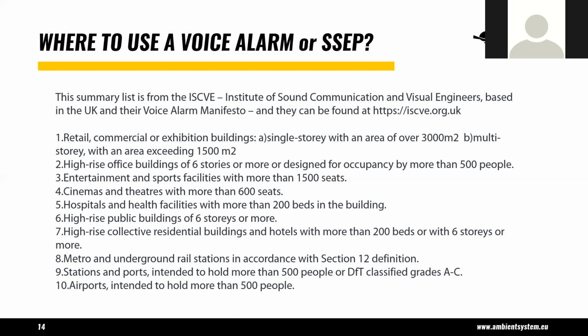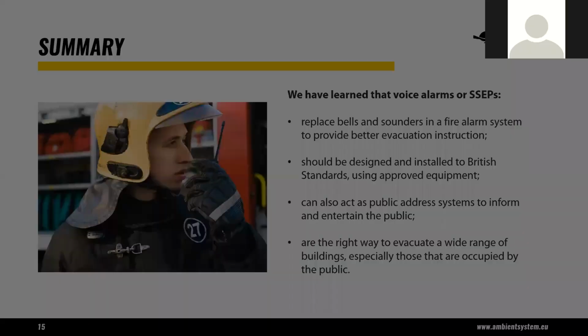So again, retail, commercial, exhibition buildings, particularly when they're multi-story, high-rise, entertainments and sports, cinemas, larger hospitals, and again, anything where the time to evacuate is longer, because high rise, by definition, gives you a longer time to evacuate. And once you turn the lifts off, which pretty much happens whenever you have a fire event, you start telling people to come down 10 or 12 flights of stairs in an orderly fashion, and that takes time. So this is why the high rise is a strong contender in the list of buildings for having voice alarm systems.